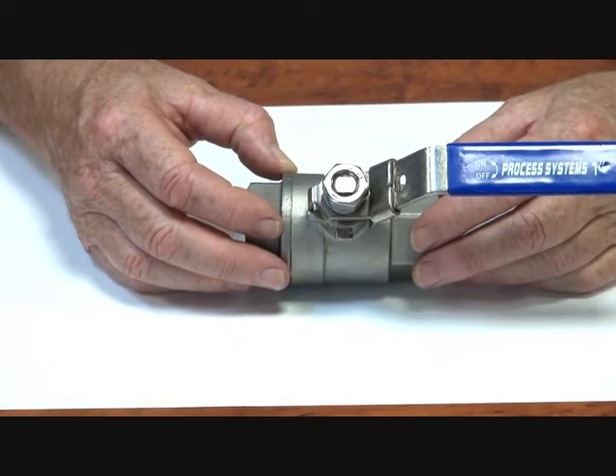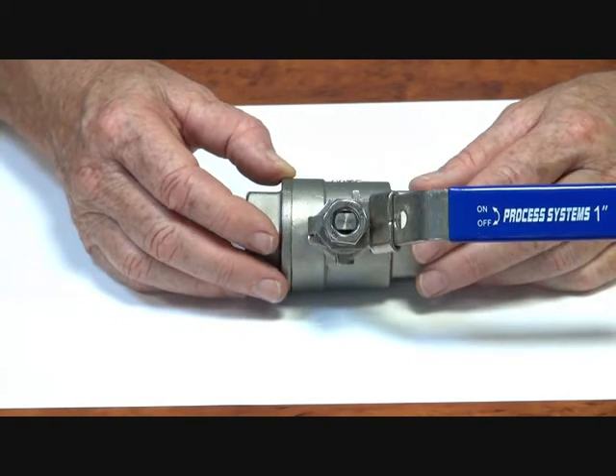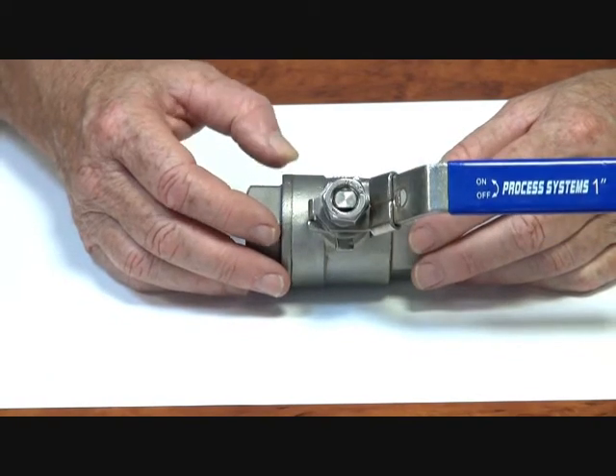So it's across and the valve is closed off. This unit here is suitable for pressures up to 63 bar, which is close to a thousand psi. 316 stainless steel, has PTFE seats and Viton backing ring.